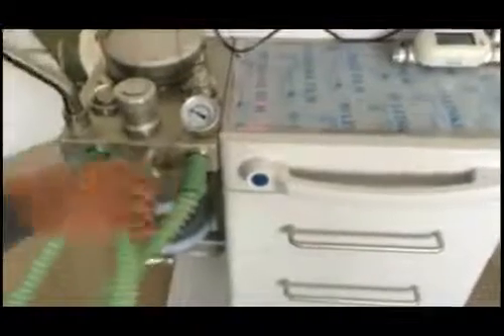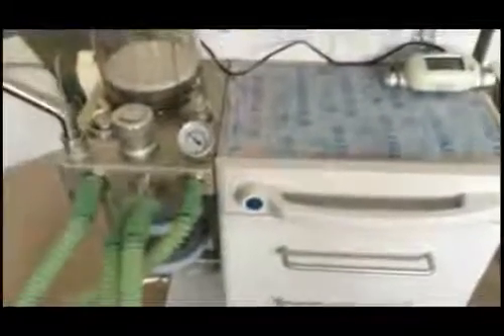Connect a tube to the inspiration port. Connect a tube to the expiration port. This is the Y piece. Connect the Y piece to the T point. Now, set the flow meter, set the APL valve to 70 cm of H2O. This is the APL valve.